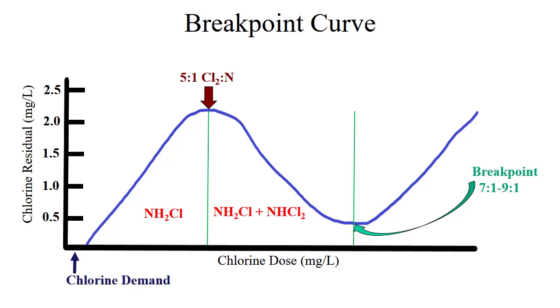Breakpoint is defined as the point on the curve where the combined and free chlorine concentrations are zero. However, with many waters at breakpoint, the DPD chlorine residual test does not indicate a zero total chlorine residual due to chemical compounds created from adding chlorine and ammonia to the water. These compounds interfere with the test and cause a false positive by indicating there is a disinfectant residual in the water when one does not exist. The curve shown here indicates a chlorine residual of 0.5 at breakpoint, but this is for illustrative purposes only. The total chlorine residual at breakpoint depends on water quality and will vary from utility to utility. As more chlorine is added past breakpoint, the hypochlorous acid and hypochlorite ion concentrations increase at a 1-to-1 ratio. If 1 mg/L of chlorine is added, the free chlorine residual will increase by 1 mg/L.